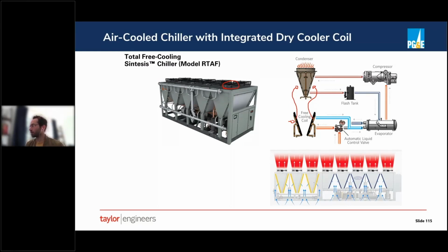Another approach that some other manufacturers take is to separate the free cooler out into its own bank of coils that's independent from the coils that are used for the condenser. And this allows us to, for instance, run these coil fans as hard as we want to provide as much free cooling as we can without consideration for that head pressure control constraint. The downside, however, is that now the system has gotten a little bit bigger because it takes up a larger footprint.